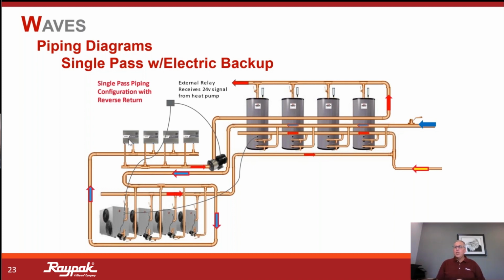But in this application, when we no longer have those multiple passes active, and we need to get in a single pass that stored water temperature, this is a configuration that's being introduced as a single pass. So when these heat pump water heaters can no longer keep up due to ambient air, then our electric point of use can be engaged. And then we now have in one pass reloading of that tank and then on out to that system.